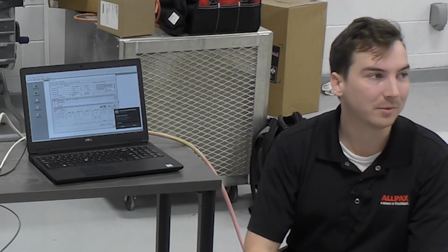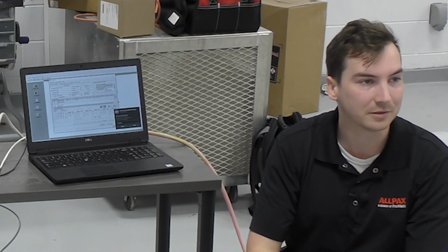And what I've noticed with mine, with longer cook processes, that temperature will slowly drop down to 250, and then you get nervous watching it because you think, oh my God, if this goes below 250, I'm in trouble. And then it just kind of levels right out. So you can set the safety factor bias to whatever you're comfortable with. We just set it to 1 degree. And again, you've got a much more reliable boiler in this building. I've not seen any problems where it even came close to losing temperature.